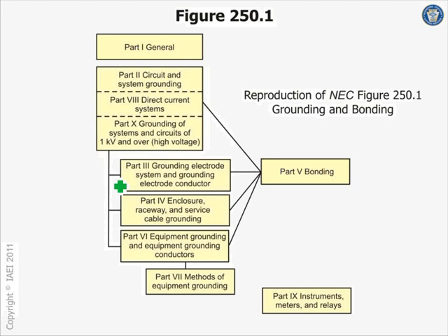I can summarize it to you in two things, two systems, either multiple grounding for the neutral or single grounding for the neutral. That's what they use. So that's the funny thing, on the high voltage end, circulating current, not a big deal. So you can take the 13A, bond it at one location and bond the neutral at the other location. Luckily, in most of the buildings that we use, guys, we do not use the neutral over 13A.